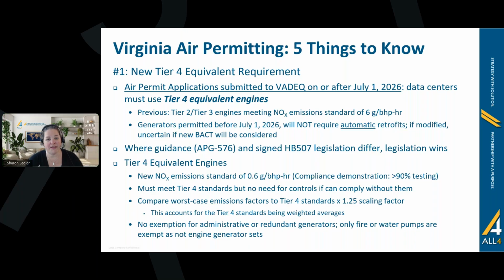The goal with Virginia DEQ is that your worst case emission factors will result in a pound per hour in your permit that you can comply with during your stack testing. It's more of an apples to apples comparison by looking at that emissions data compared to the Tier 4 standard with a multiplier.